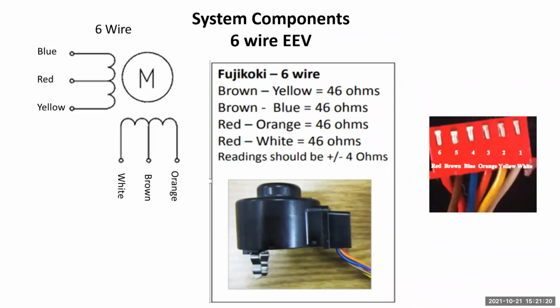Checking your EEVs. You want to pull the plug off the board and check to see what you have. This is also in your service manual, and you want to have around 46, usually around 40 ohm, or not 40, my apologies. Around 50 ohms is good, but you want to check between brown and yellow, you have 46, brown and blue, 46, red and orange, 46, red and white, 46. But if you check between, in this particular case, orange and white, you will probably wind up getting 100 ohms. That's nothing to freak out about. You're just reading the full extent of that winding. And once again, please always check it to ground.